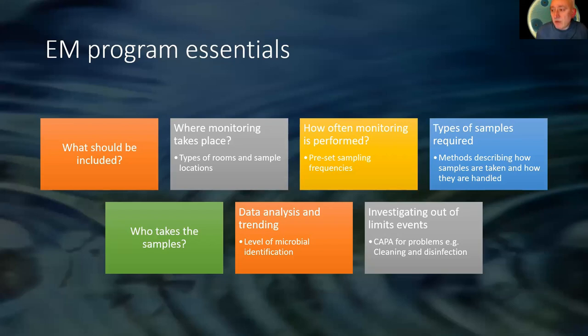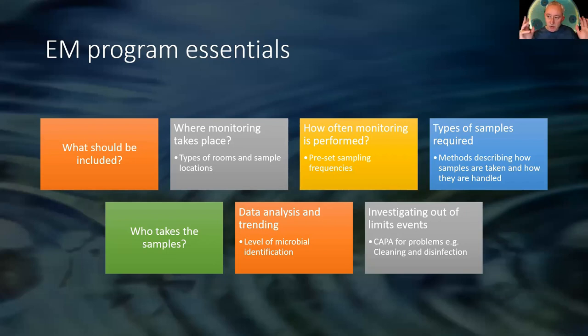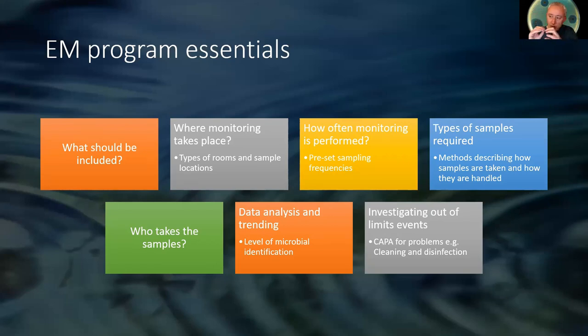In terms of the essentials of environmental monitoring, we should determine where we're going to monitor and how often. We know that for aseptic processing, monitoring must be continuous. For other types of clean rooms, we might want to do ambient rooms more often than cold rooms, rooms with open processing more often than closed processing. We need to look at process flows — where does equipment go, where do people go — to help determine where to monitor and what the most appropriate sample is. Techniques like HACCP (hazard analysis and critical control points) can be very effective for helping to determine monitoring locations.